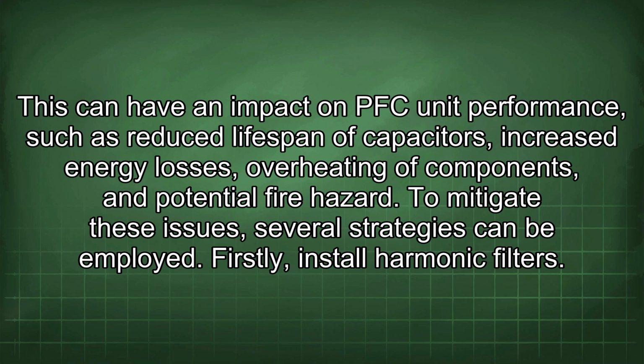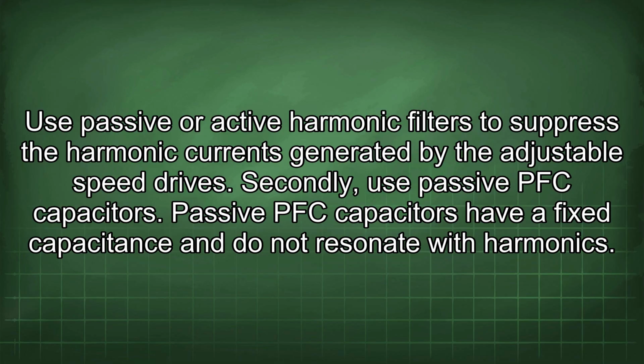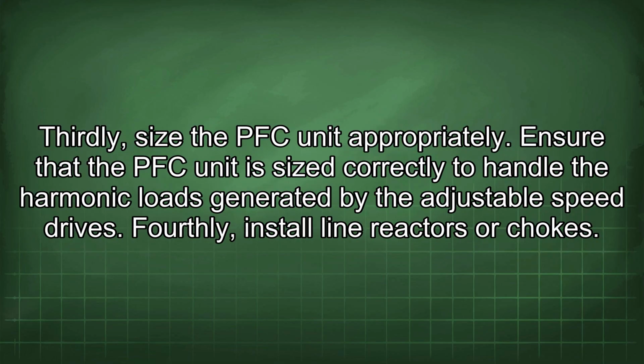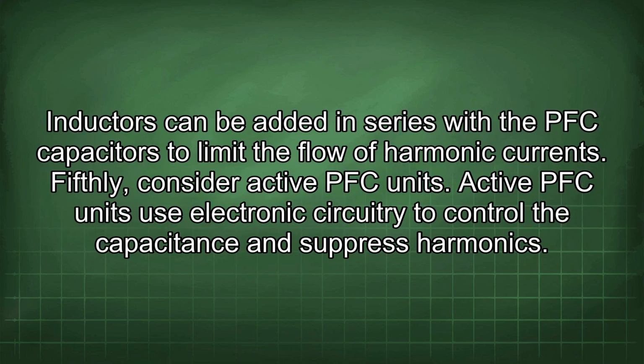Firstly, install harmonic filters. Use passive or active harmonic filters to suppress the harmonic currents generated by the adjustable speed drives. Secondly, use passive PFC capacitors. Passive PFC capacitors have a fixed capacitance and do not resonate with harmonics. Thirdly, size the PFC unit appropriately. Ensure that the PFC unit is sized correctly to handle the harmonic loads generated by the adjustable speed drives. Fourthly, install line reactors or chokes. Inductors can be added in series with the PFC capacitors to limit the flow of harmonic currents.